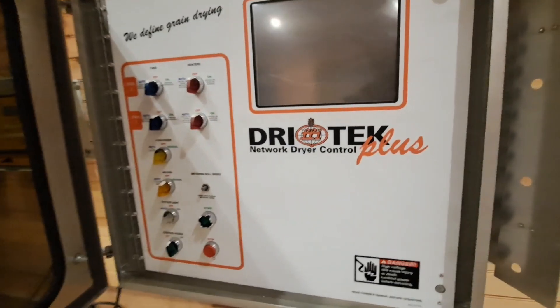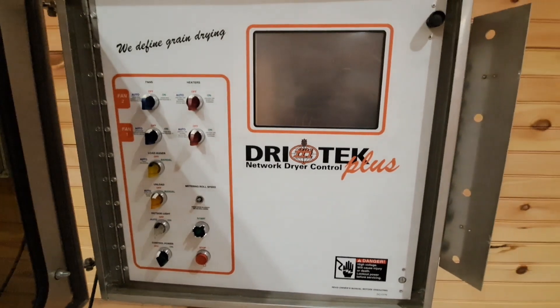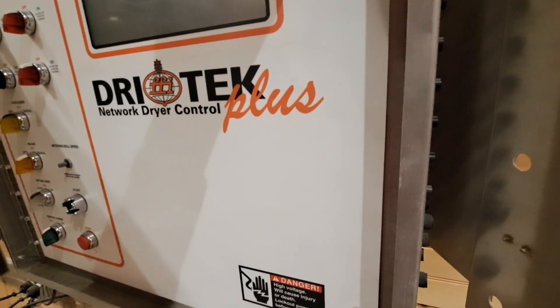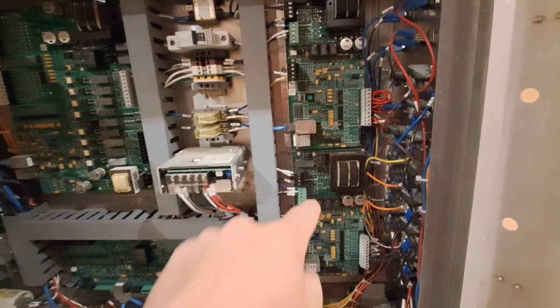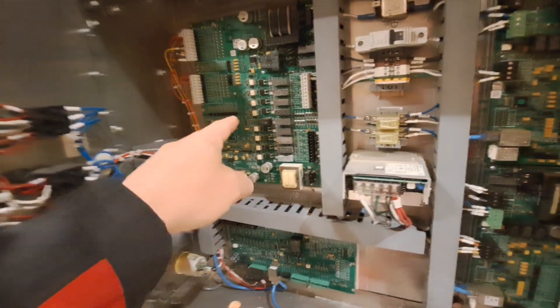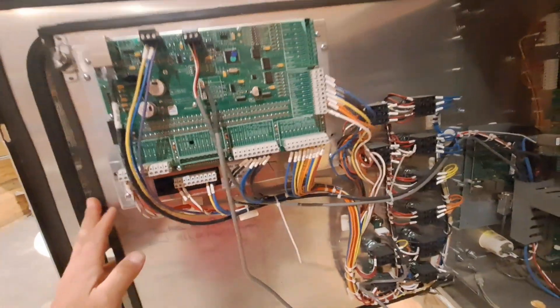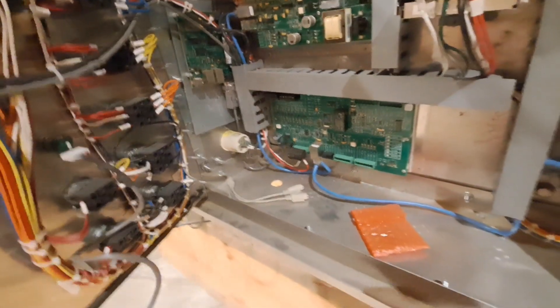If you have a Farm Fans DriTek Plus network dryer control or a GSI Vision Control and you've replaced any of the boards — this is a demo unit, so we have our fan heater boards in here and our network main IO board, which you normally wouldn't have. Normally it would just be this stuff here and possibly your moisture board if the controls are mounted on the dryer.